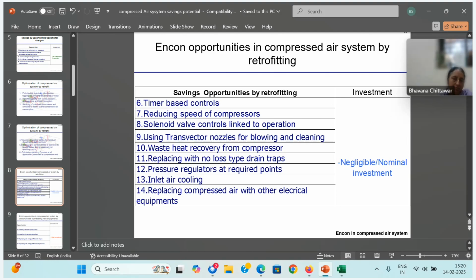Then inlet air cooling. See, by cooling the compressor room by 1 degree, you can save 3% of the energy. Sorry, 3 degree cooling will result in 1% of savings. So instead of ambient 37, if ambient conditions are 40 degree, you lose 1% energy. So you can think of inlet air cooling, or keep the room cool by smart modification of compressor piping or ducting the hot air outside. So these are the options available.